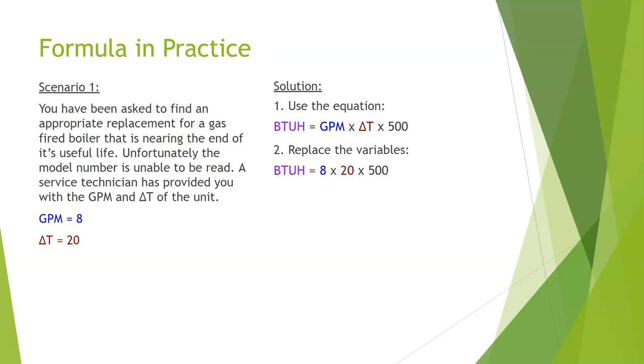The second thing I do is replace my variables. BTU equals 8 GPM times delta T of 20 times my magic number of 500. Now I work the formula. BTU equals 8 times 20, which gives me 160, times 500. That gives me a BTU of 80,000 BTUs. This is notwithstanding any efficiencies or AFUEs. We work it very simply just like our HVAC airflow calculation. It works in the exact same way. Our variables are just a little different.